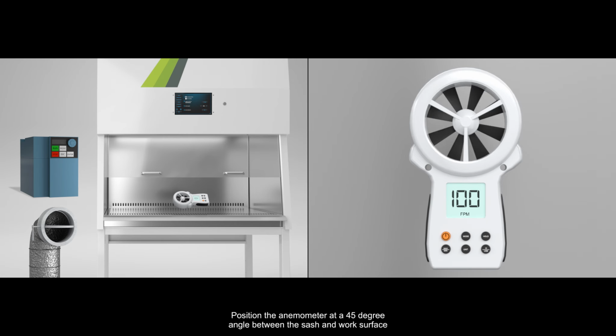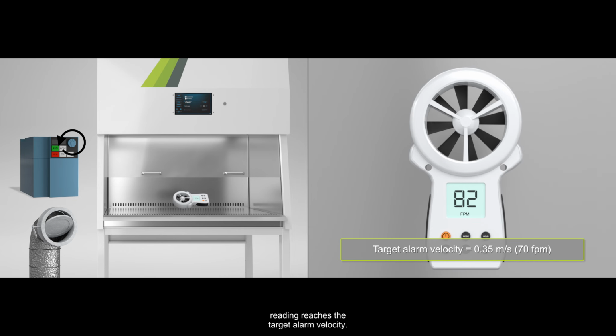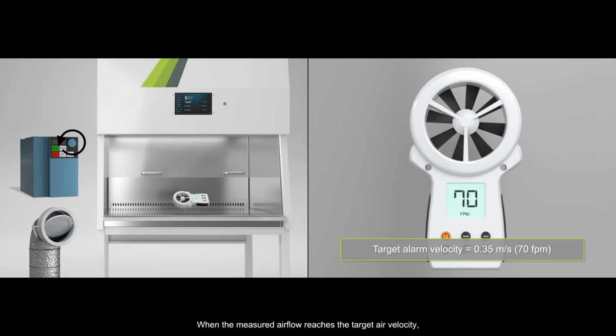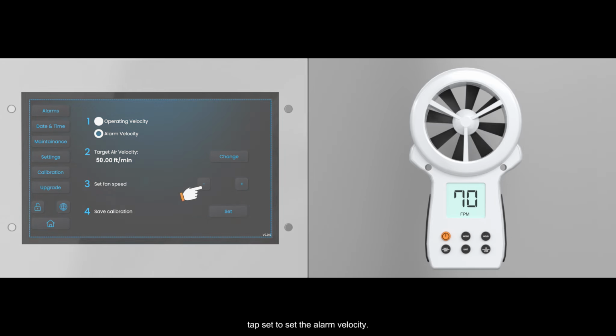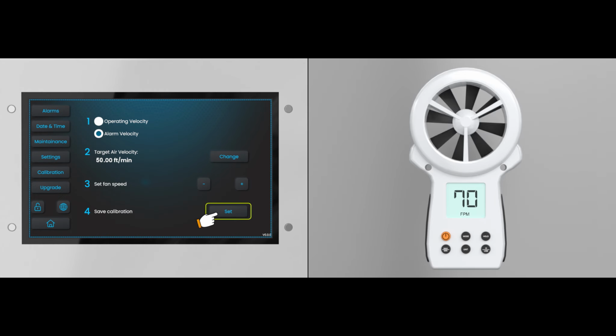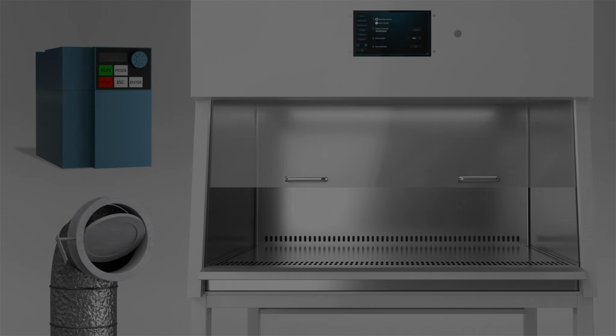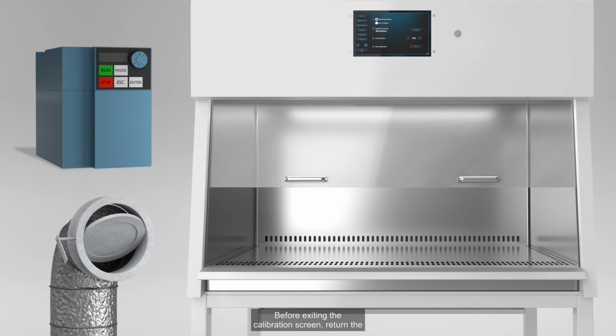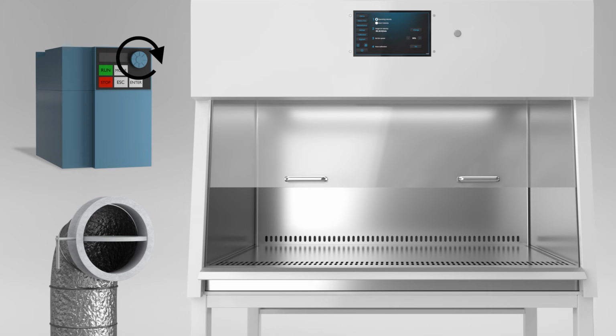Position the anemometer at a 45-degree angle between the sash and work surface and lower the external blower until the anemometer reading reaches the target alarm velocity. When the measured airflow reaches the target air velocity, tap Set to set the alarm velocity. Before exiting the calibration screen, return the damper or VFD to the operating velocity position.